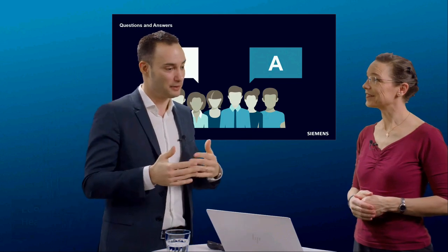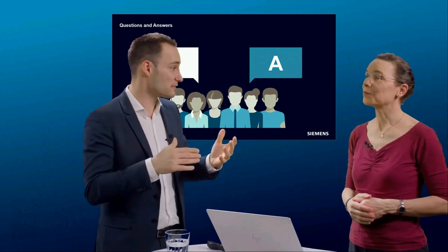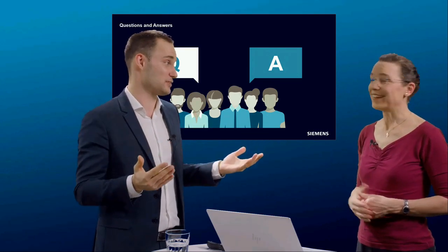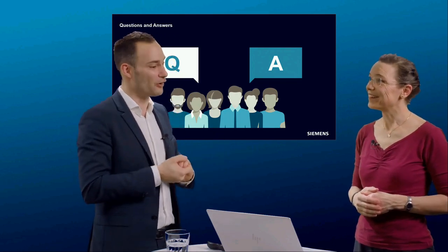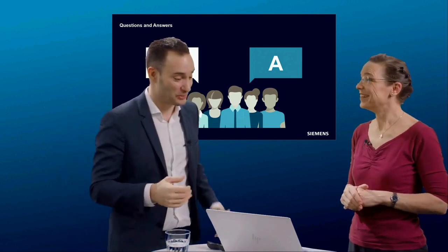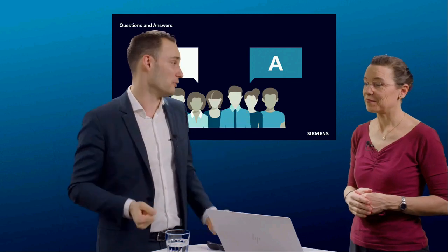If we compare air vacuum to some other components, we don't have this liquefaction stage that some of our colleagues can face with SF6. If you go too low in temperature, SF6 gas will liquefy. As we have vacuum, we don't have this issue. So it's a perfect fit for us. We are very pleased today to have a lot of our GCBs installed at down to -40. That's also a selling point which is very important for our customers, because they can have our GCB installed outside at -40 without any other protection than the GCB itself.